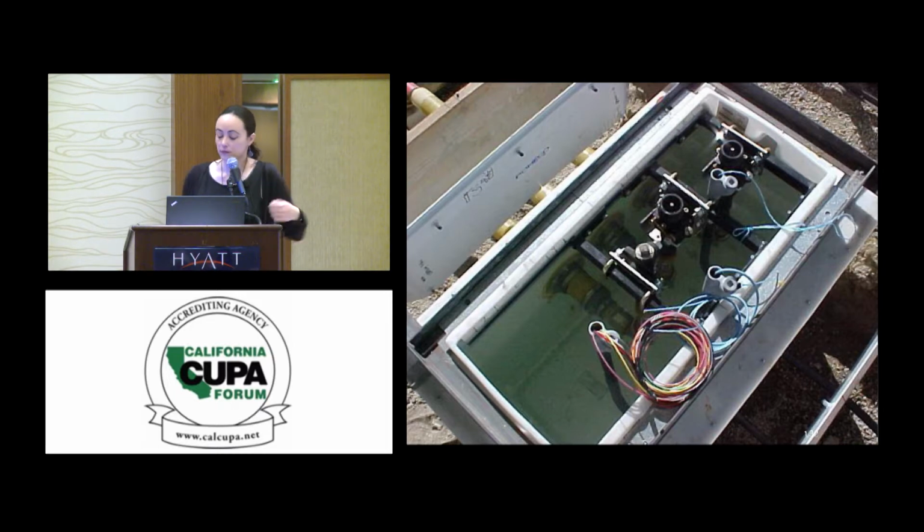In this photo, I don't know if you can see, but there's liquid in here because this was a new installation. You can see the piping here, still the pea gravel here. So they're testing, and this would be similar to the spill containment. This would be a leak test or a visual hydrostatic test. So they just fill up the UDC with water, and they have to observe if there are any leaks, by either walking around or with soap, like the soap water test on all the fittings on the outside, or maybe there's leak water draining out on the walls on the outside, or you can also check for moisture on the ground, and then you can figure out if there's any leak.